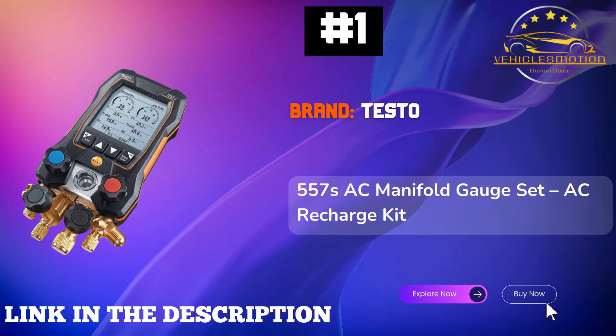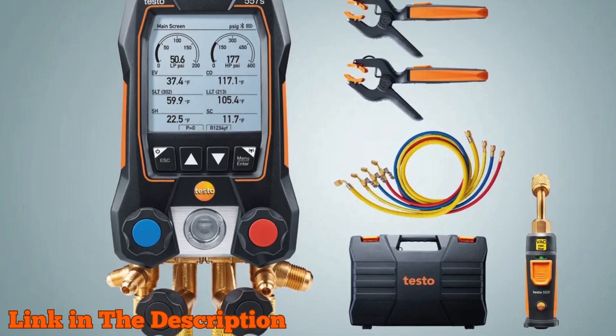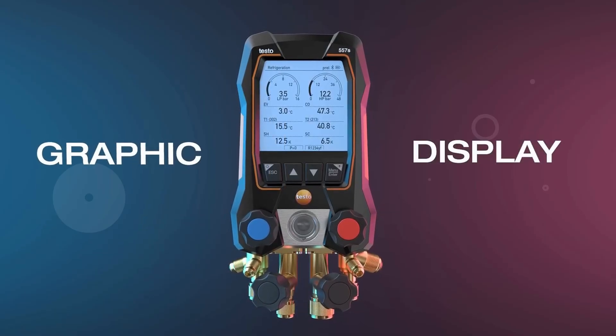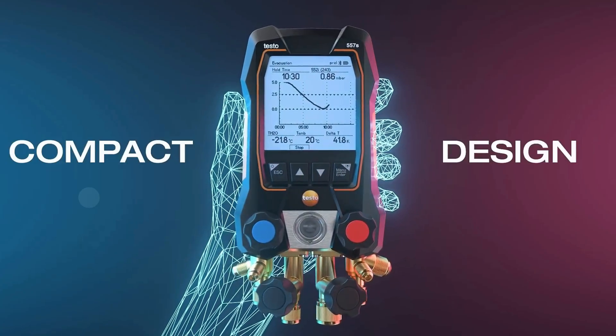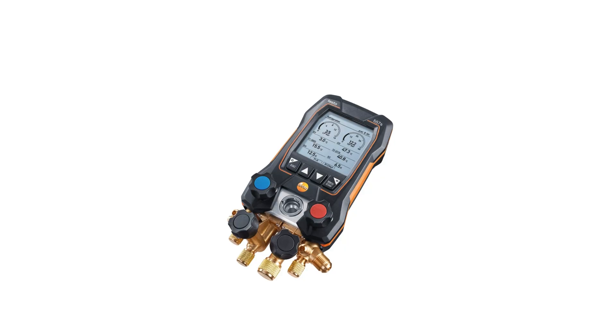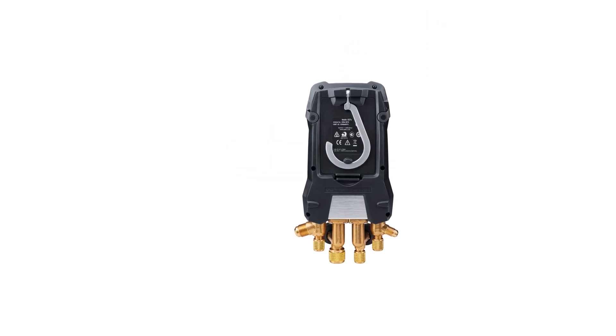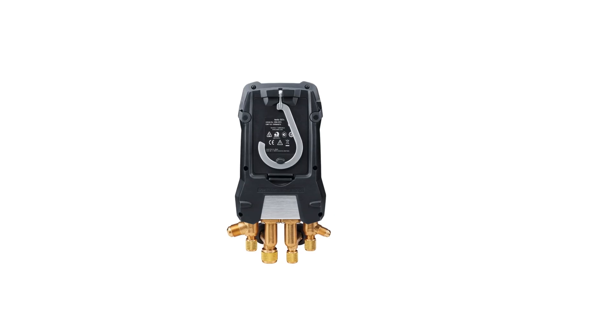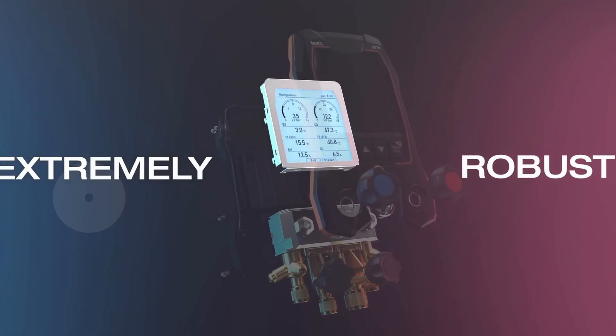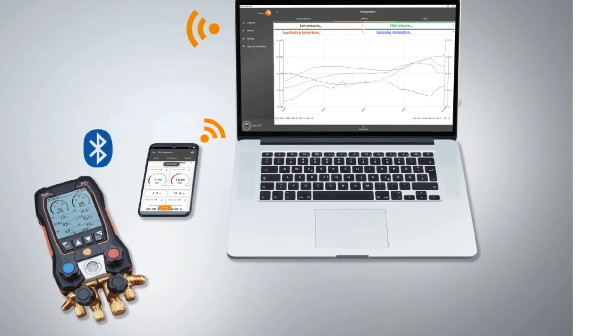Number 1: Testo 557s AC Manifold Gauge Set — the ultimate tool for HVAC professionals seeking precision and versatility. This exceptional AC recharge kit combines two 115i pipe clamp thermometers and a 552i micron gauge, ensuring you achieve the best performance for refrigerant systems and heat pumps. With an intuitive menu and four-way valve block, accessing hard-to-reach pressure points has never been easier. The micron gauge's impressive measuring capabilities include temperature accuracy of plus or minus 0.9 degrees Fahrenheit and pressure measurements precise to plus or minus 0.5 percent of the full-scale value.